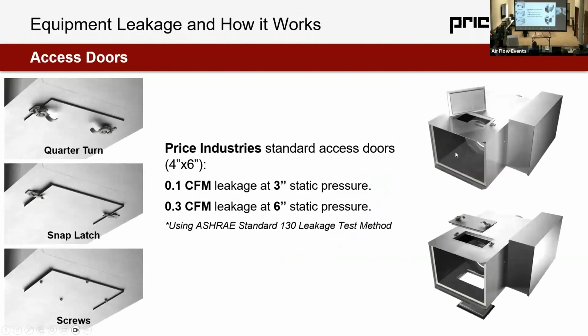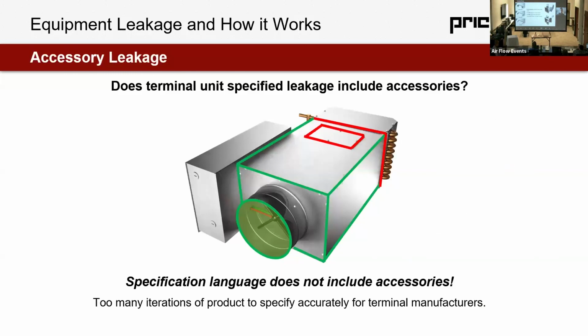So do I have to have the contractor seal that? And if I have them seal it, does that nullify warranty that I have for your piece of equipment? Not for sealing. So, transverse joints, 95% of the time are managed by the contractor in the field. Sealing those joints will have no impact, I'll say with 100% confidence, on Price equipment warranty. I'll say with 90% confidence on any manufacturer. I don't think anyone's going to void warranty or have warranty issues with the sealing of transverse joints whatsoever. I'd be disappointed if another manufacturer did. I don't think it's likely.